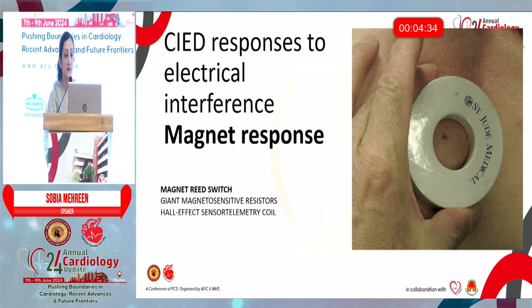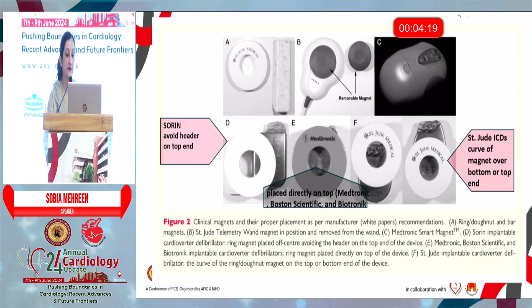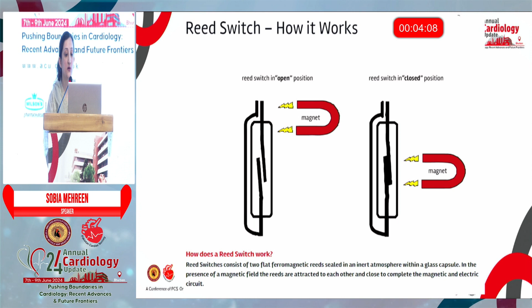Since I have been discussing magnet placement in the previous slides, I will briefly touch on the magnet response and how it works. The magnet, a 90 Gauss magnet, can be placed directly over the device in case of Medtronic, Boston Scientific, and Biotronik devices, and it is placed off-center in Sorin and St. Jude's devices. The magnet works by causing activation of the magnet reed switch. When the magnet reed switch is in the closed position, it causes the magnet response to occur.